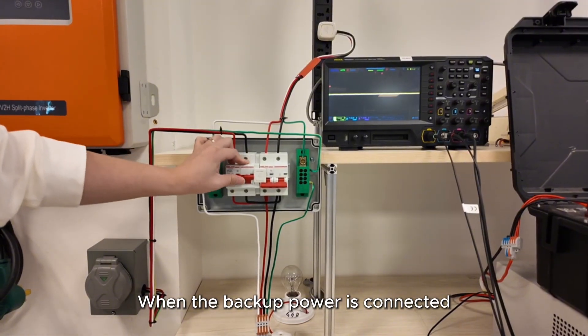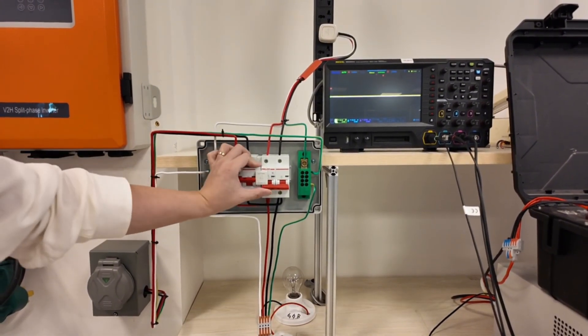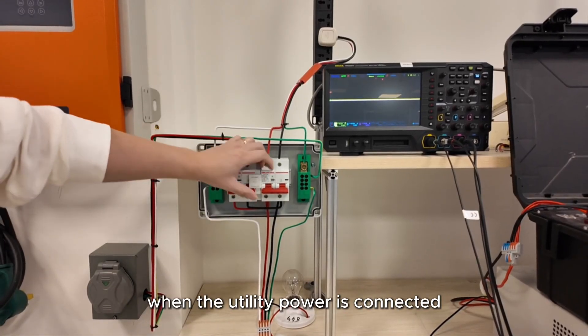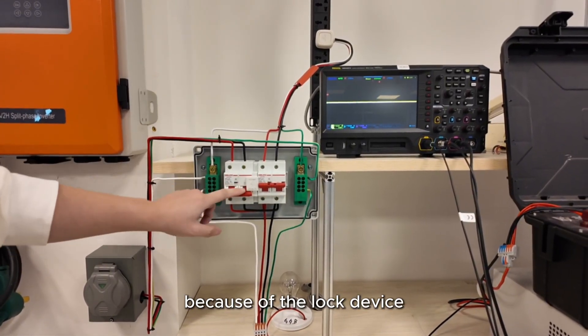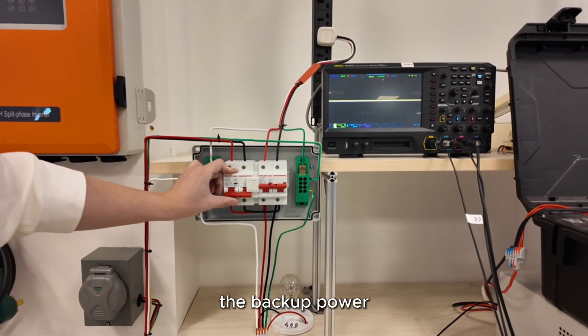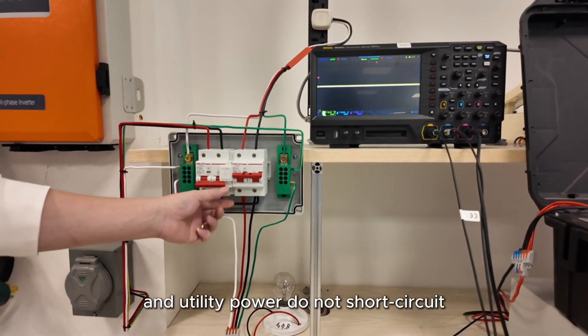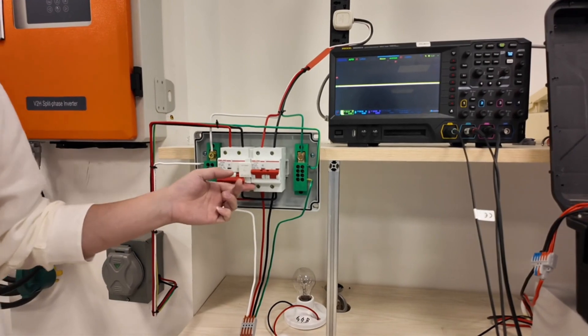When the backup power is connected because of this lock device, the utility power cannot be backfed. Likewise, when the utility power is connected because of the lock device, the backup power cannot be backfed either. This ensures that backup power and utility power do not short circuit.